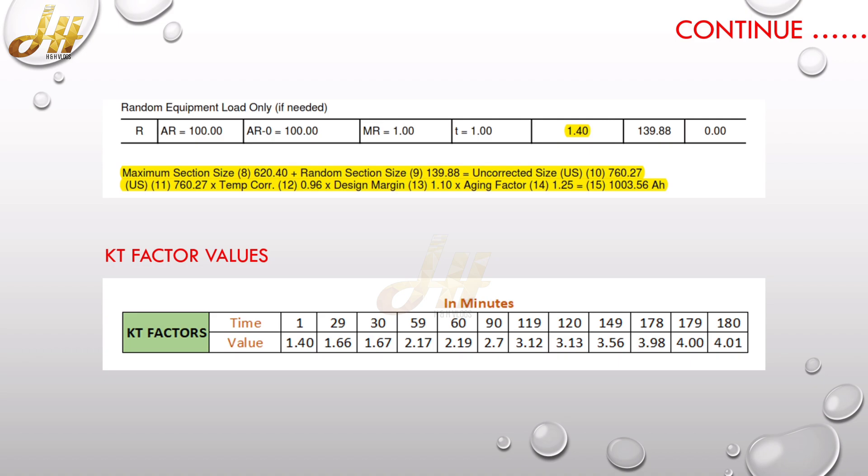So this is the uncorrected size. This uncorrected size is then calculated with temperature correction factor, design margin, and aging factor, so that we got the value of capacity as 1003.56 Ah. So the next higher capacity of the battery will be selected.